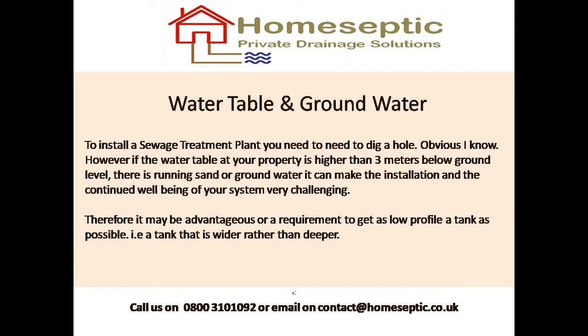If your water table is higher than 3 metres below ground level, or there's running sand or groundwater, it's going to make installation really difficult, potentially dangerous for an installer. Therefore, the engineer needs to understand if you have an issue with groundwater. If you do, it's not the end of the world. What we'd normally do in such a situation is look for a tank that is as shallow as possible. So, for example, Marsh do a shallow tank, which is only 1.6 metres deep, which requires a lot less digging than, say, a normal Graf tank, which is 2.8 metres deep.